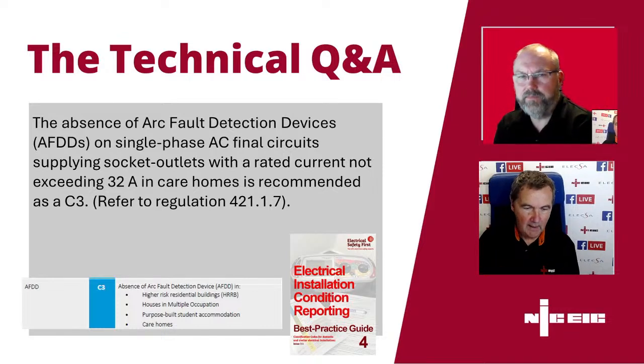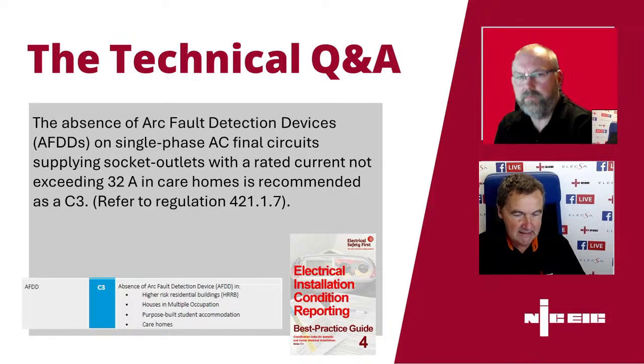We should have mentioned this before when we referred to the recommended classification code for a lighting circuit without CPC - we always suggest Best Practice Guide 4. It's published by Electrical Safety First, but produced and agreed by an industry standard group, ourselves included, colleagues from ECA, Electrical Safety First, NAPIT, the IET, BEAMA. So it really is recognised industry guidance, and that also recommends a C3.